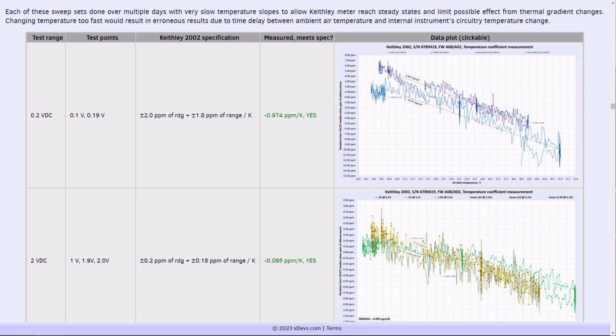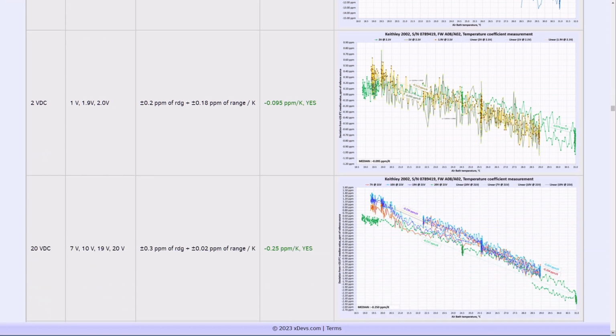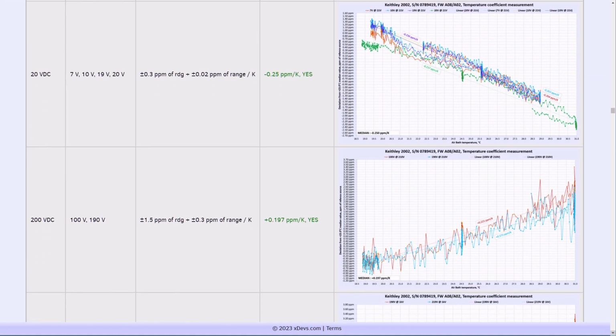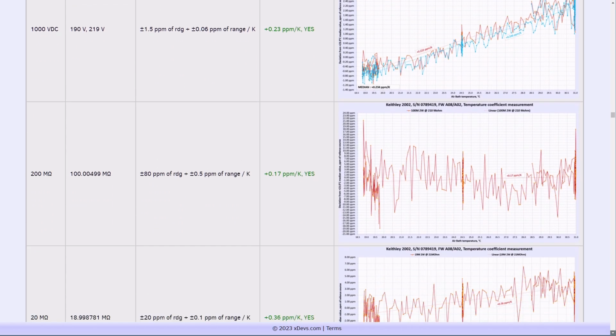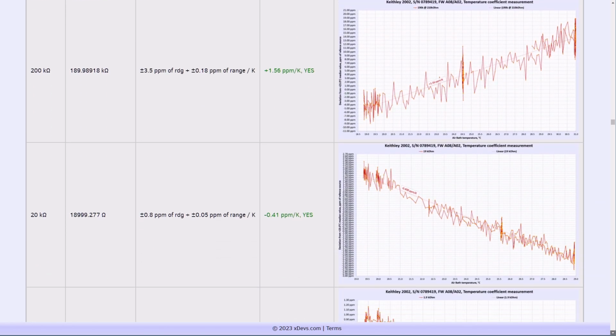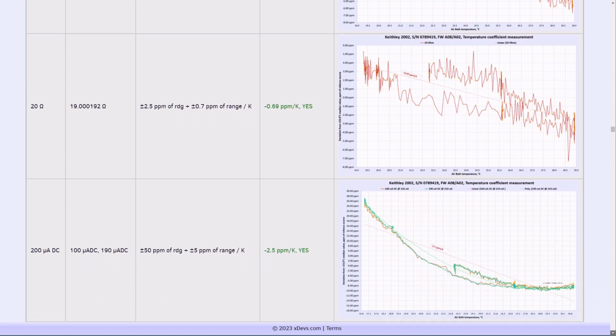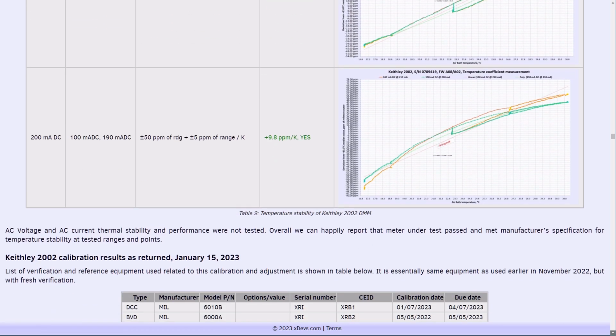execute. Results for these tests for all DC voltage, DC current and resistance function ranges were presented in article table 9. Best thermal stability is achieved on 2 volt range with tempco just minus 0.1 ppm per degree, followed by higher voltage ranges at minus 0.25 ppm per degree.